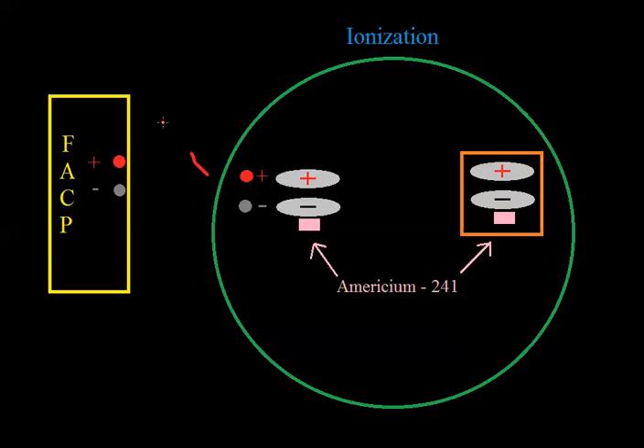What that element does is it ionizes the air in the chamber, hence the name ionization smoke detector. Bear with me, I'm going to try to explain what that means. First of all, let's power this up. Same panel, same 24 volts going to our smoke detector, nothing fancy. Let's take our 24 volts and go to these two metallic disks. This is now a positively charged disk, and this one on the bottom is a negatively charged disk because we tied it to our power source.